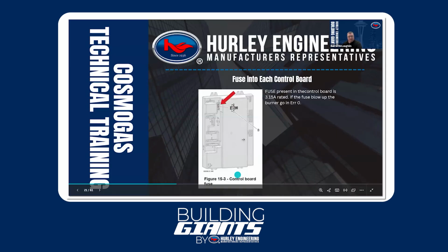And then one more fuse just built into our flame safeguard, and that's right here, and that's commonly overlooked. But on the low voltage side, if you ever have wiring issues or shorts or grounds or things like that, this is the fuse that generally pops, and you always want to check on that one. And that's going to be built in our control boards, mounted right on the front of the burner, or front of the boiler.